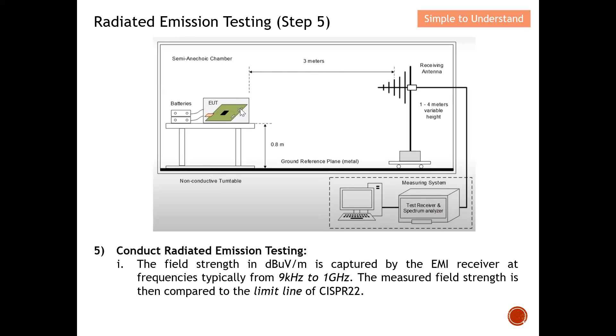For the detailed final scan, the turntable turns more slowly and the antenna height is varied finely — for example, from 1.00 meters to 1.01 meters, 1.02 meters — to find the antenna height that produces the maximum radiated emission from the EUT. The turntable also rotates to find the facing direction with the maximum value. With that maximum value, all readings are tested by the EMI receiver to determine pass or fail. If the reading is lower than the limit line, the test is concluded as passed.